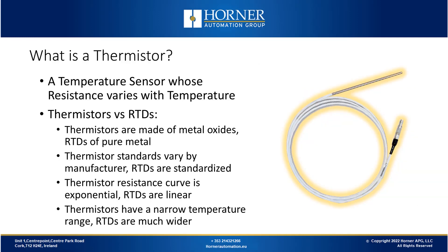A thermistor is a temperature sensor whose resistance varies with temperature, which is the definition of an RTD as well. So we'll compare the similarities, but primarily the differences, between thermistors and RTDs. Thermistors are made of metal oxides or combinations of metals, whereas RTDs are usually pure metals. Thermistor standards vary by manufacturer, whereas RTDs are more standardized. If you buy a PT100 RTD from a manufacturer, the same PT100 specification from a different manufacturer will yield roughly the same results — that's not always true with thermistors.